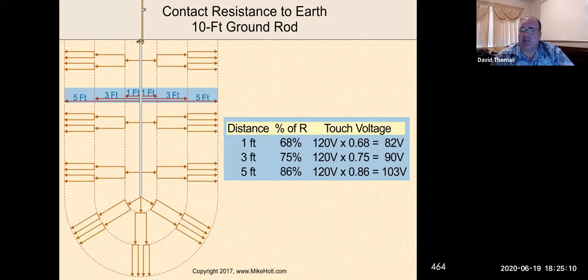Okay. And the other thing about this effect, which is kind of interesting: if you put a ground rod into the earth, how the dissipation of the electrons occurs is somewhat like in this method, and voltage drops according to the further you are from the ground rod. The voltage will drop.